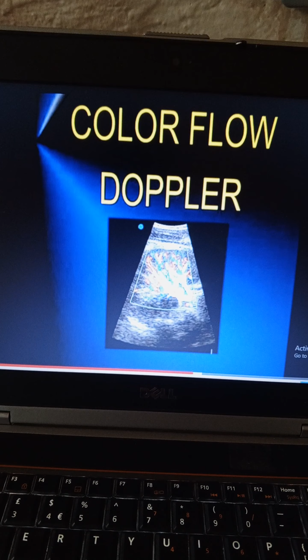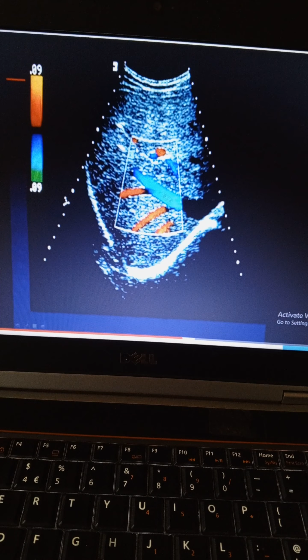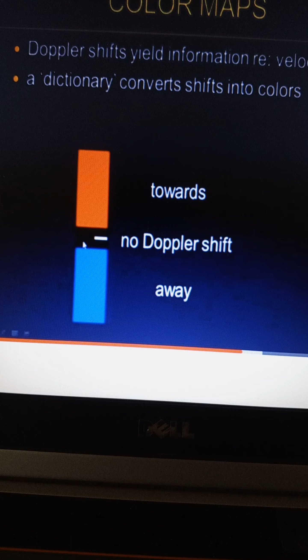Color flow Doppler is directional, so it depends on the flow of blood. If the flow is towards the transducer, the color will be red, and if the flow is away from the transducer, the color will be blue. This is how it is represented, and we always look at the color bar box on the machine. The red tells you that flow is towards the probe or the transducer, and blue is away from the transducer. So red towards the transducer and blue away from the transducer. These are the color maps that we find on our machines.